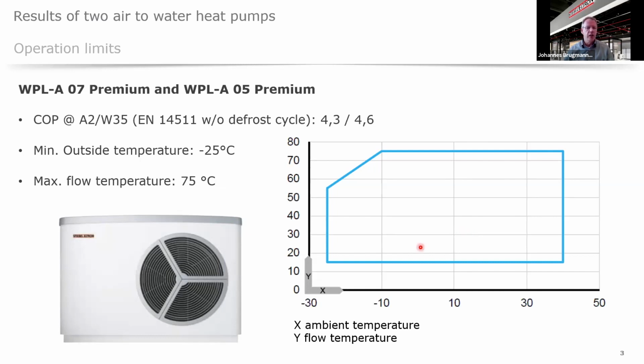Then we achieved a minimum outside temperature of -25 degrees, so we can use these units also in colder climates, and the beauty of this is the limit of the flow temperature. The maximum flow temperature is 75 degrees, so we can use these units in applications of old buildings, and we can ensure a hygienic hot water supply without any problem. So to reach 60 degrees in the tap water tank is no problem.